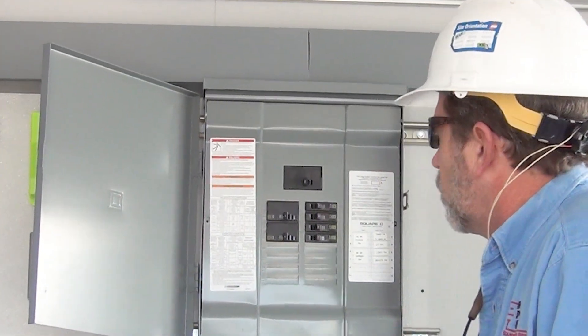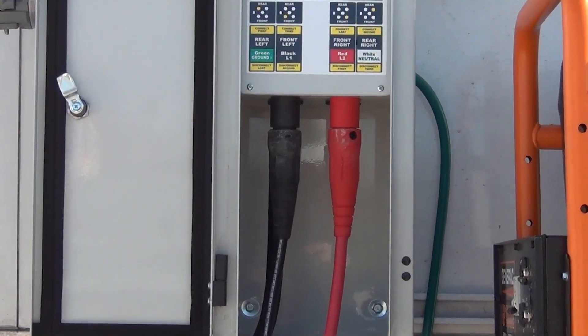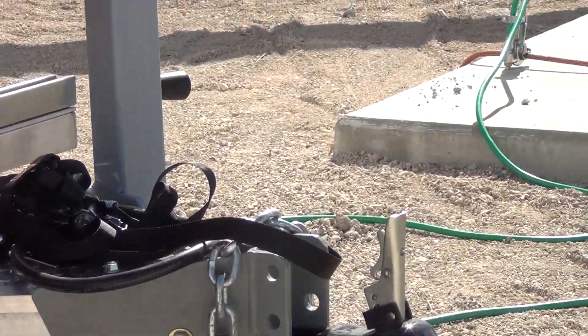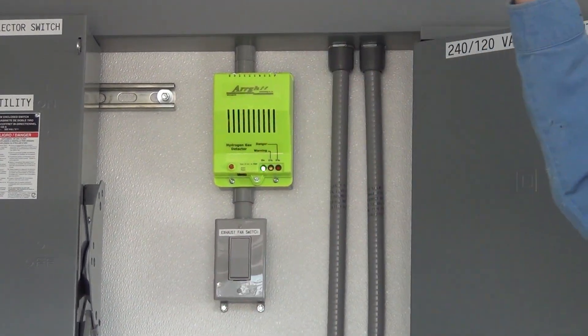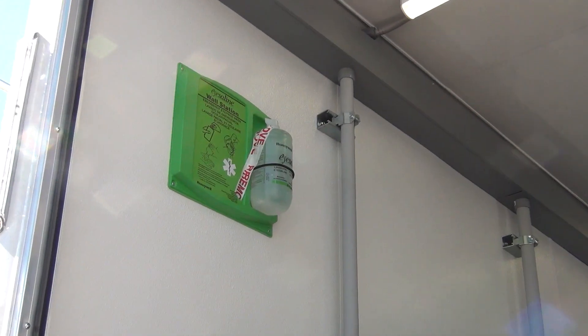We also integrate a 120/208/240/480 VAC distribution system with external cable port and cable, a DC output disconnect switch with overcurrent protection, external DC cam lock connection points, external ground termination plate with cable and clamps, and custom length DC output cables on reels with cam lock connectors. Hydrogen detection with automatic start of ventilation fan and shutdown of battery chargers and rectifiers is also included.